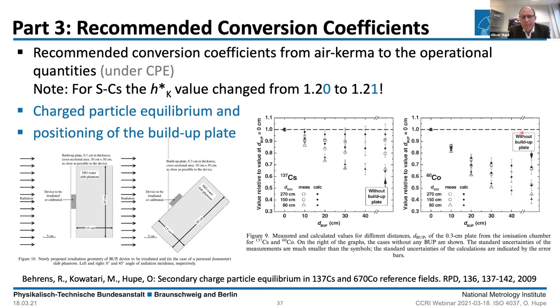And if you are far away, it's the same as if you don't use a build-up plate, you can be off by 40–60%. For sure, this also depends on the distance from the source. If you are far away, you have a lot of air, there's air scattering, so building up electrons, so then you get charged particle equilibrium without a build-up plate. But this is very difficult, and it would depend on the distance and so on. It was decided: use a 3 millimeter build-up plate in any case, and you will always be in the right situation.